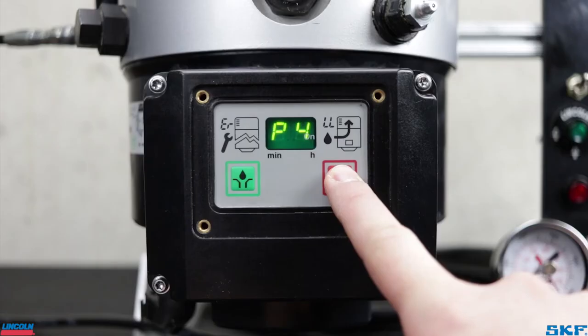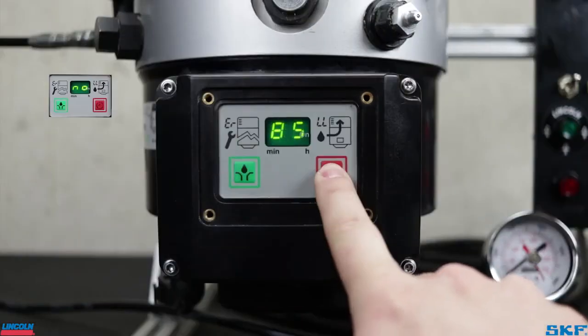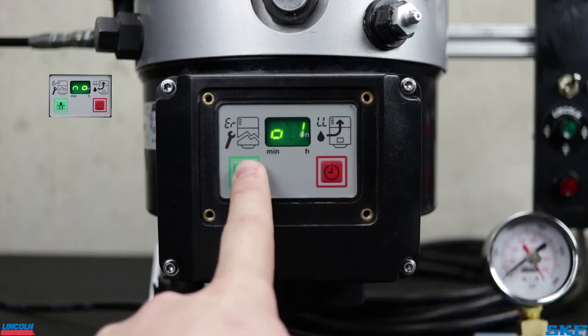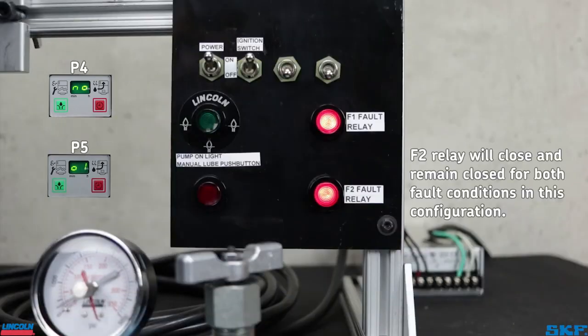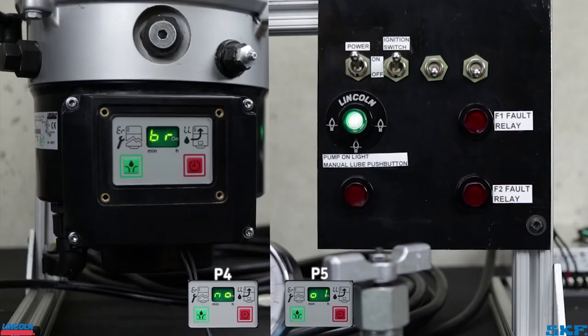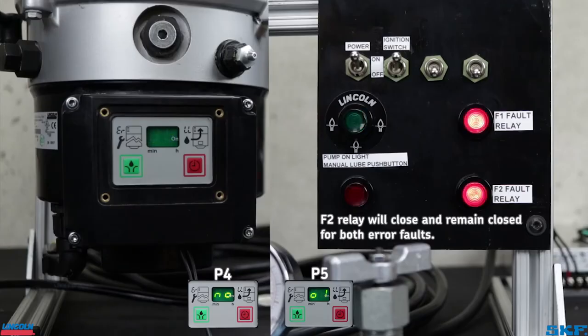Now leaving P4 at normally open, but setting fault signaling to O1 or option 1, this is now setting the F1 relay contact up to receive both faults in the form of codes. If a low level trips, the relay will repeatedly open and close, or in my case, flash a light on the panel. If a pressure error occurs, the F2 relay will close and remain closed, or turn on the light.